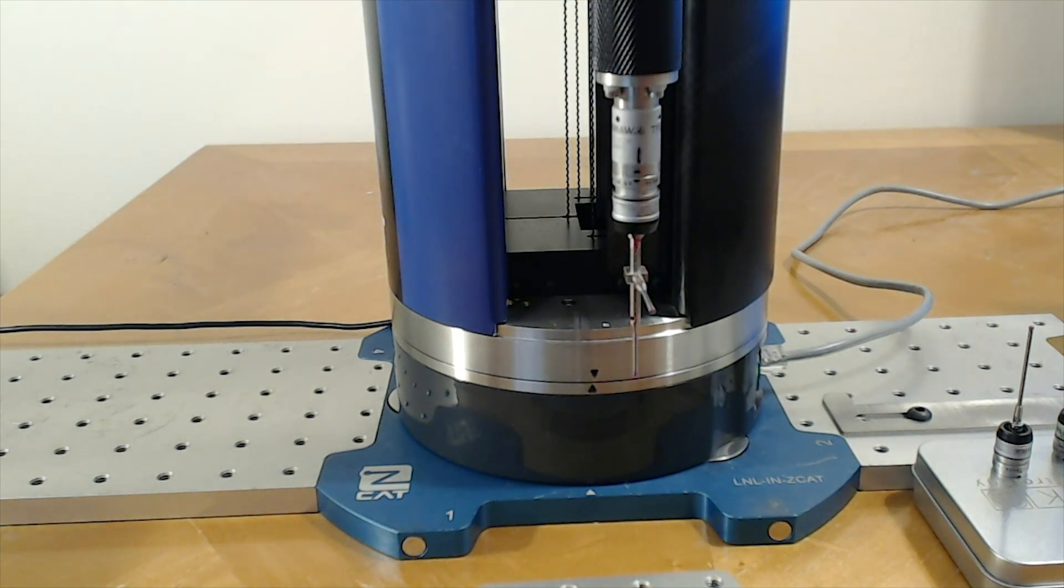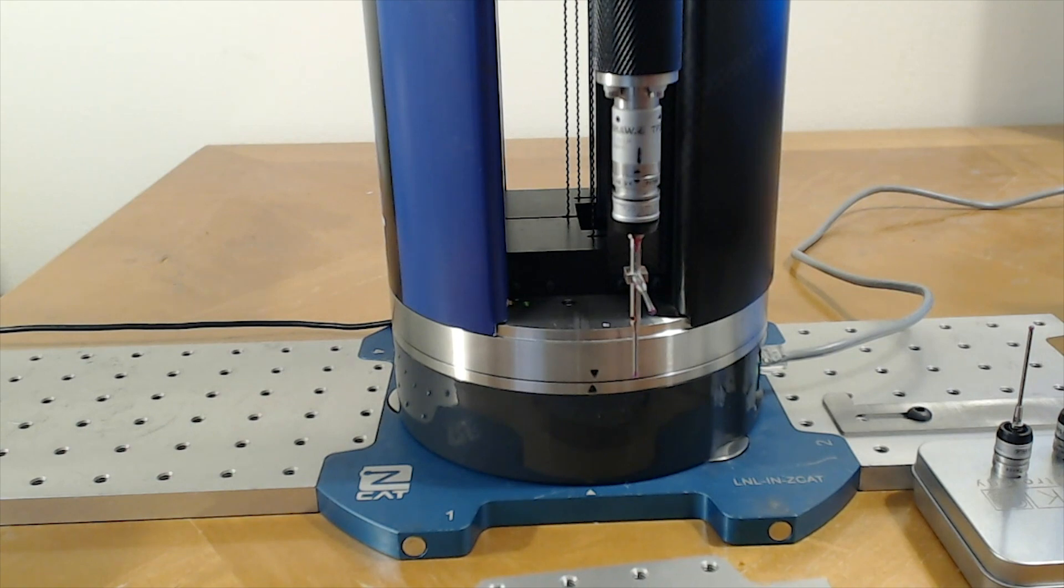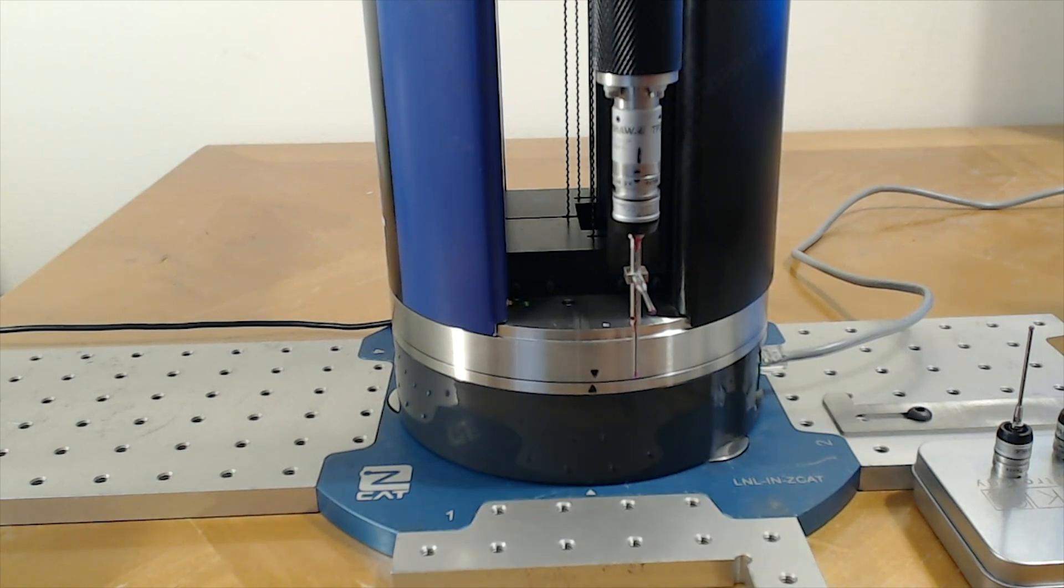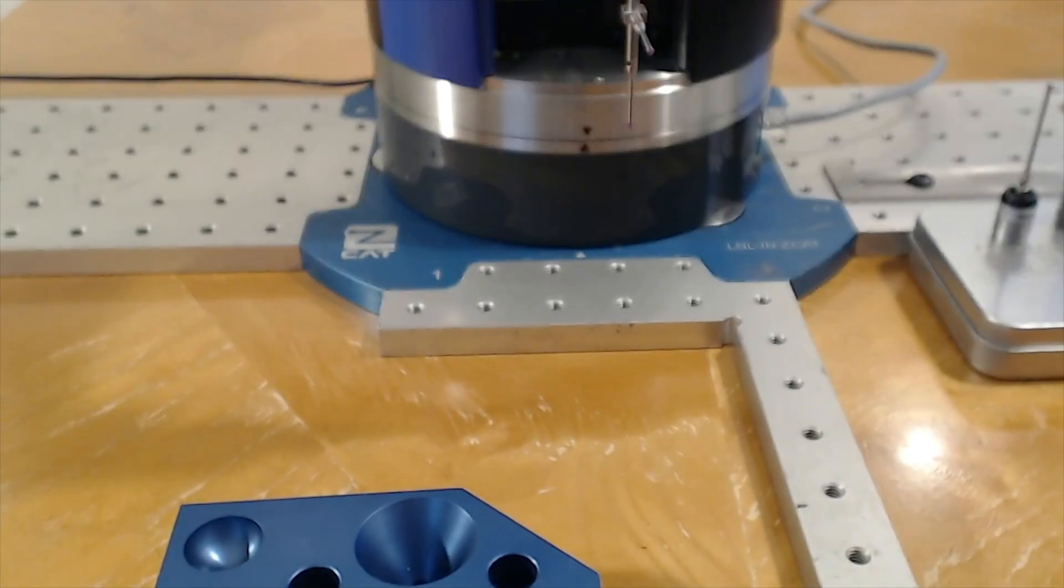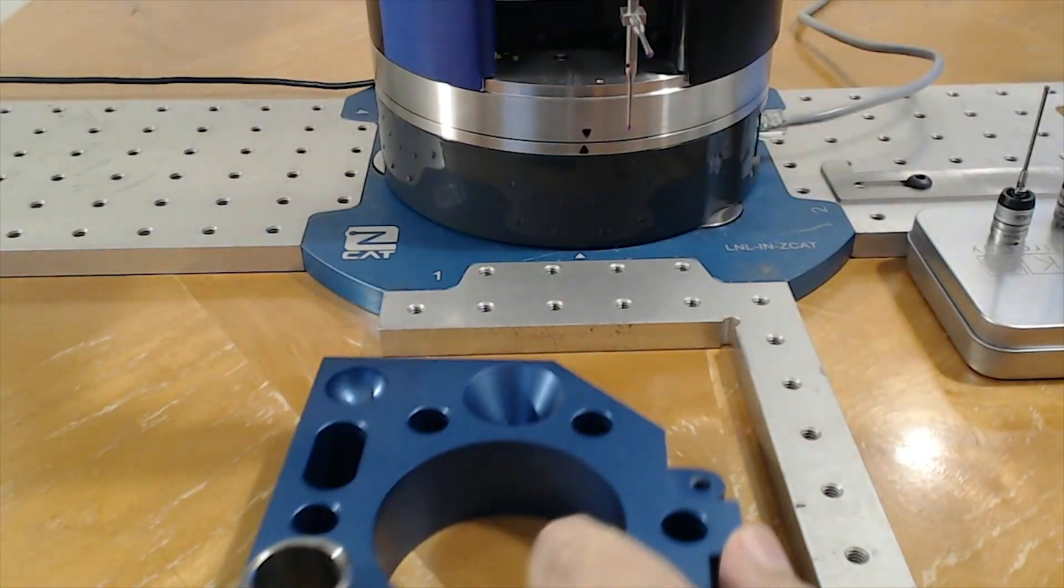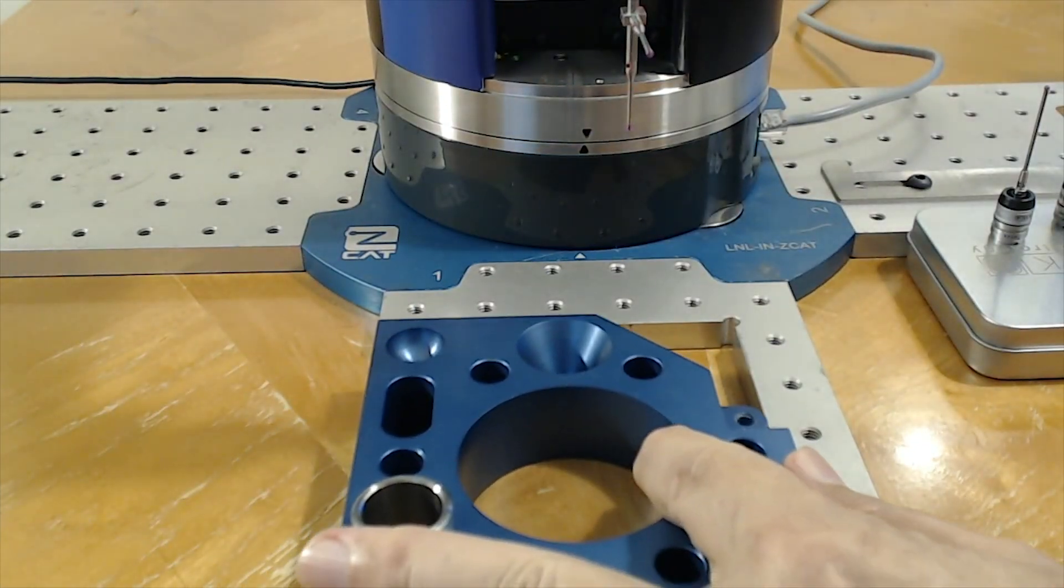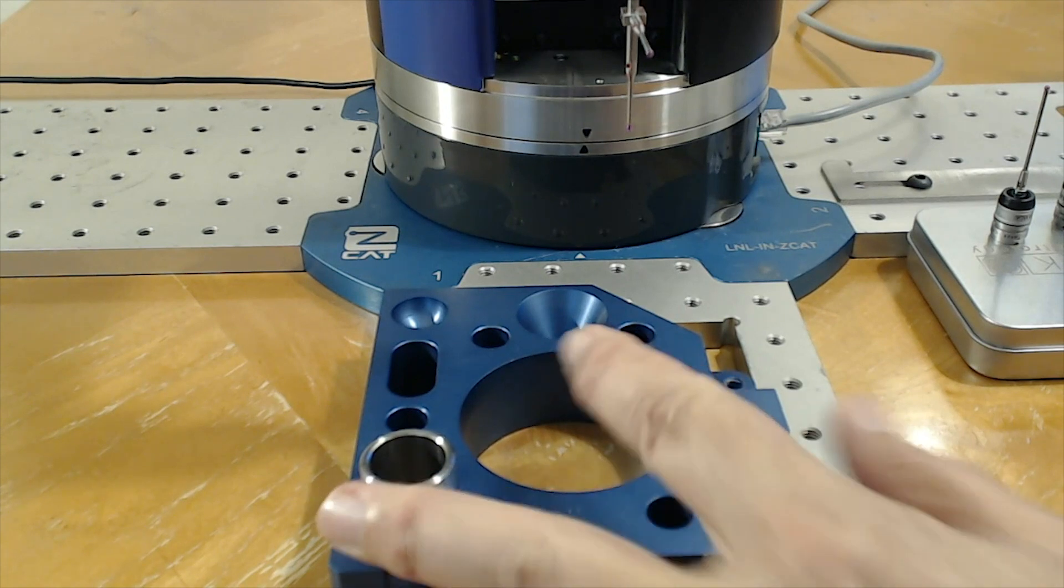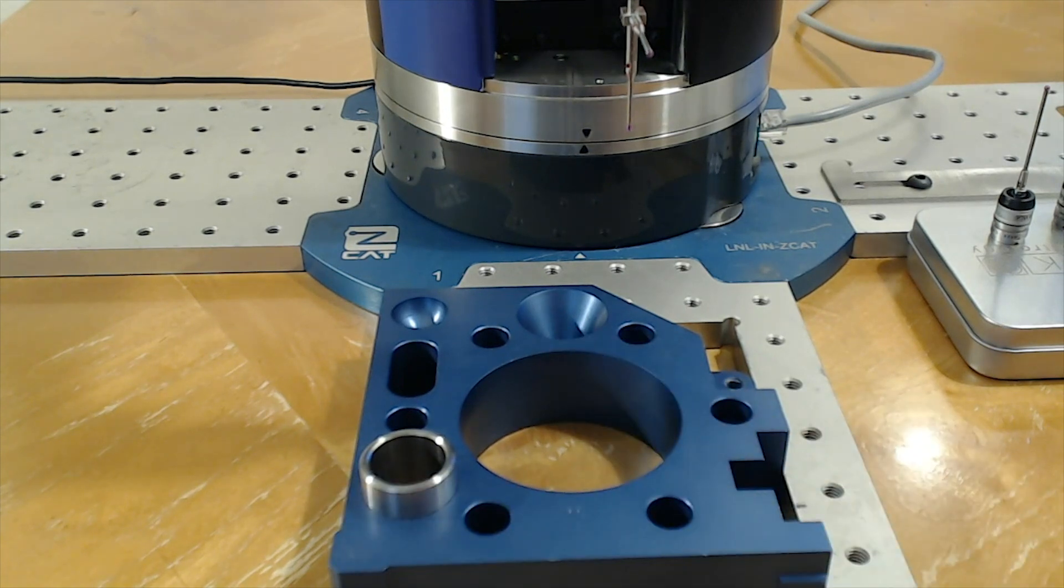So if I'm going to start measuring a part with the ZCAT, in this case I have it on the modular fixture system. I can put one of our plates in here and they're magnetic so we can get them oriented properly. In this case I'll put my part in place of it.